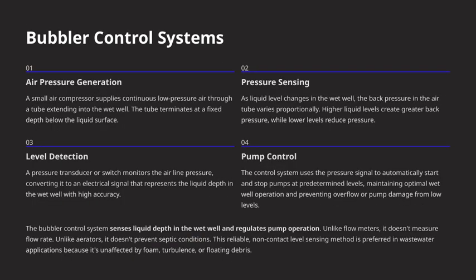Now, let's take a closer look at the bubbler control systems. First, we have the air pressure generation component. A small air compressor continuously supplies low-pressure air through a tube that extends into the wet well. This tube is positioned at a fixed depth below the liquid surface, ensuring consistent measurement.